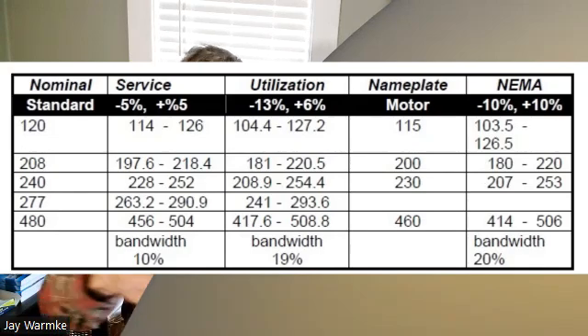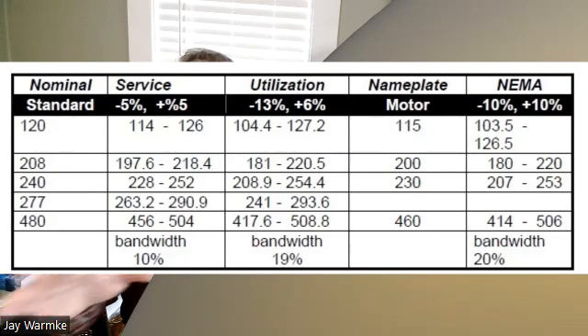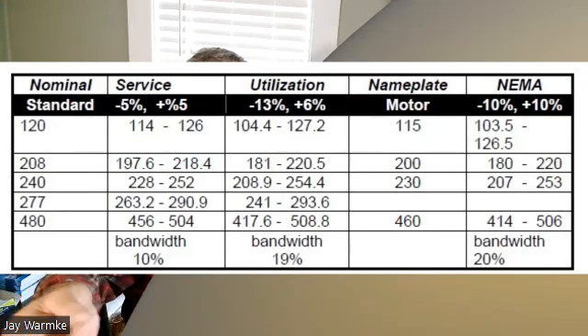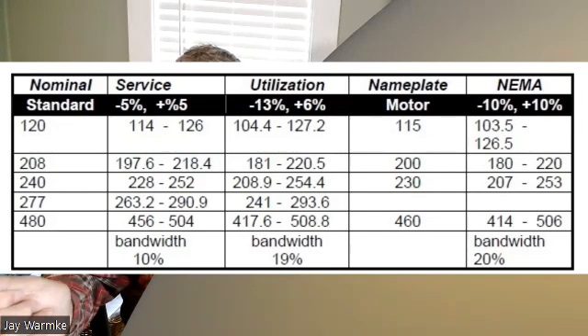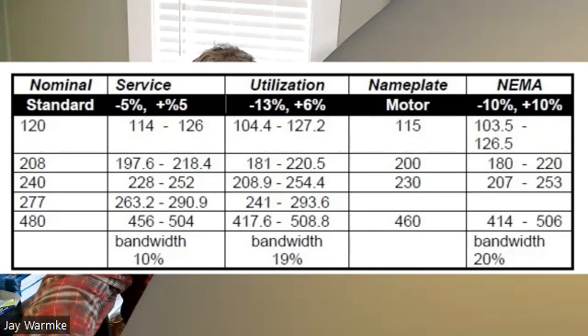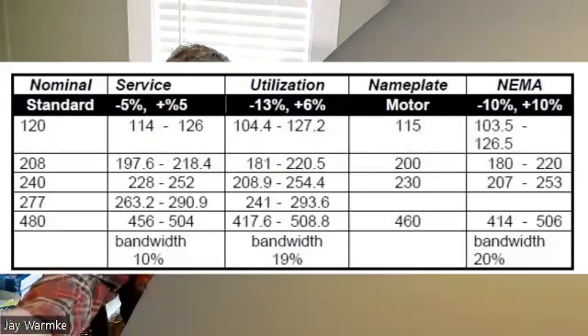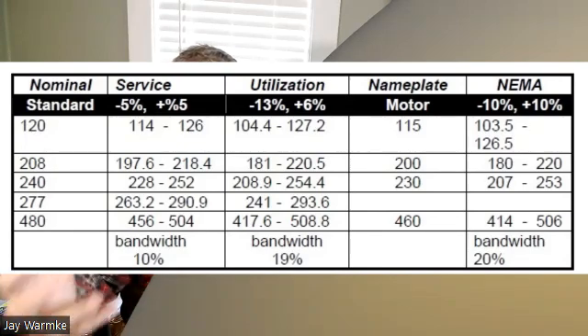That's because you can't keep it truly steady, because every time somebody turns on an appliance or turns off an appliance, it's going to affect the voltage on the system minutely. So it's always operating within a range. Well, in this particular range, if we're talking about a residential environment, single phase, 240 coming in, the range tolerance that you can see in column 1 there is that the system will typically operate between 228 and 252 volts. So that's normal grid operation.